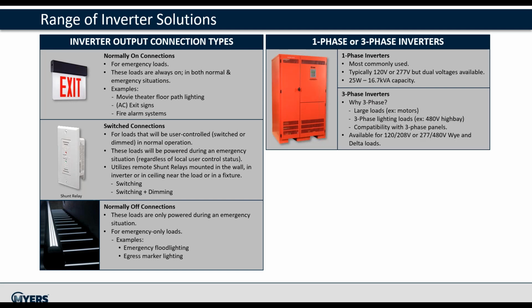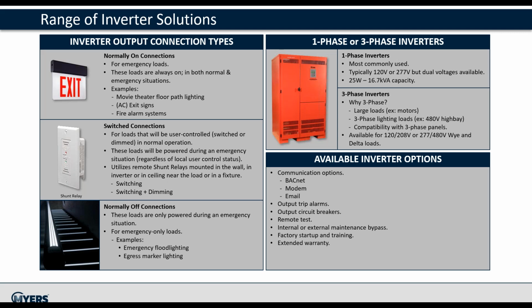Single-phase inverters are more commonly used for cost reasons, but some applications require three-phase motors, or if the current is large enough, lowering the wire gauge may make sense to use a three-phase system. Other useful options include communication options connecting to BMS systems, output distribution, trip alarms for detection of disconnected emergency loads, remote testing capability, maintenance bypass for service, factory startup, and extended warranties.